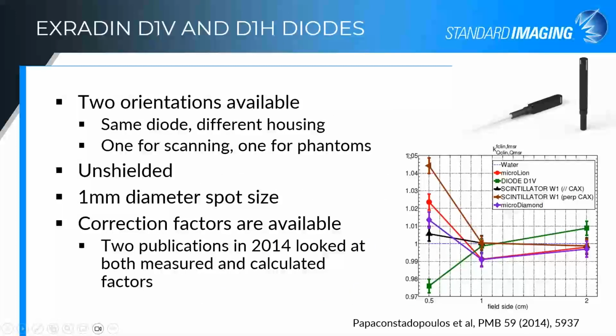So in terms of our diodes, the D1V and the D1H are the same physical diode, they're just in two different shaped housings. So this vertical one is designed for scanning so that you're not perturbing the water around the point of measurement. The other one is designed for a little bit more ease of use in slab phantoms, so that this could be in a milled out slot in a slab phantom to be able to do some closer to surface type measurements. They're unshielded diodes. They have a 1 millimeter diameter active region spot size, and there are some publications with correction factors for the D1V and the D1H.